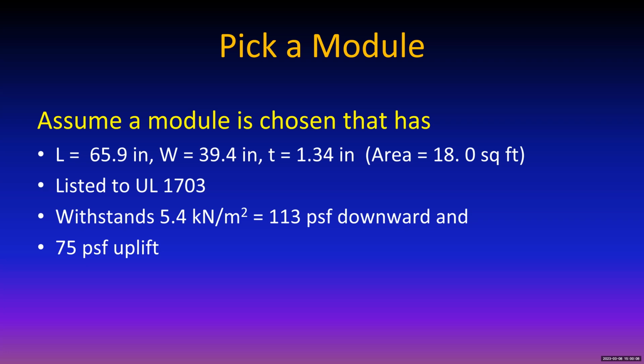The listing: 5,400 newtons per square meter, that's 113 pounds per square foot downward. Most of them have that, and it's because of the way the frames are designed. They are stronger if you push down than if you push up. And 75 PSF uplift. And the wind loading, it's the uplift that we get concerned about, because just like an airplane, it's not the wind underneath the wings that holds the airplane up. It's the suction above the wings that holds the airplane up. And it's the suction above these modules that tries to lift them up off the roof.